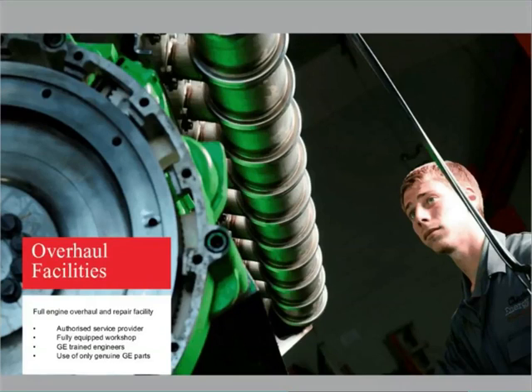So another element is how the major servicing is carried out on the engine primarily, but also the generator and other balance of plant. From our perspective on Jenbacher engines, as you'll see in the following slide, there's a service schedule that on a natural gas unit results in a minor overhaul, a top-end overhaul essentially, after around 30,000 operating hours, and a major overhaul, which is a top and bottom end, essentially a refit of an engine, at 60,000 hours. And those are by far the biggest planned service activities that occur in the maintenance cycle of the engines.